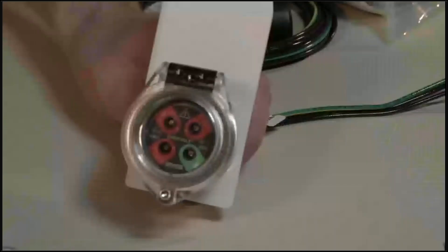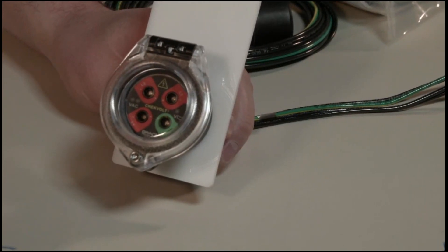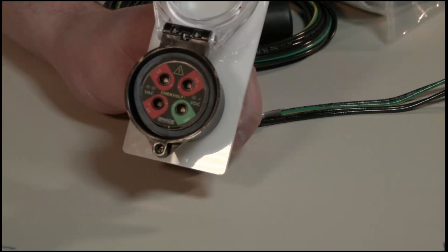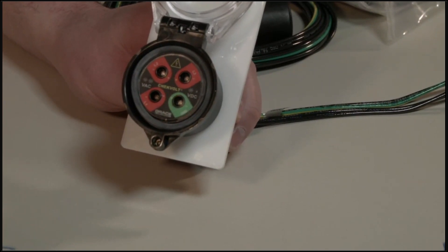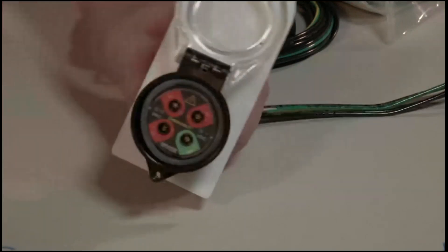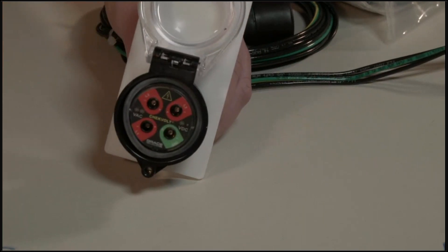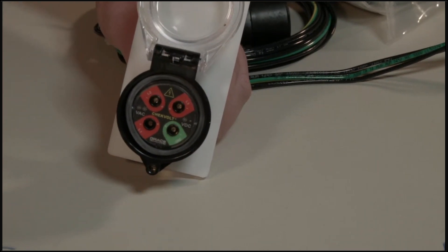The newest product we want to talk about today is our Check Volt. The Check Volt solution combines our dual redundant LEDs from our voltage indicator with our contact tester safe test point device. It's all in one easy-to-use product. It meets the standard within NFPA 70E with no exceptions, mitigates arc flash and shock hazard, and enhances your compliance. It uses a simple 30-millimeter hole punch knockout — Greenlee makes the standard hole punch you can purchase — on the outside of your enclosure, then wire the component into your equipment.